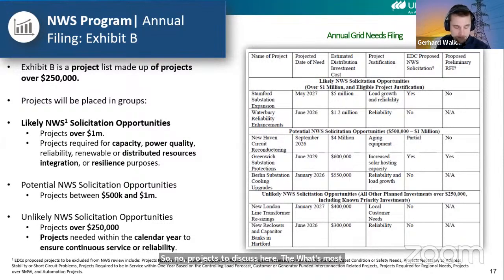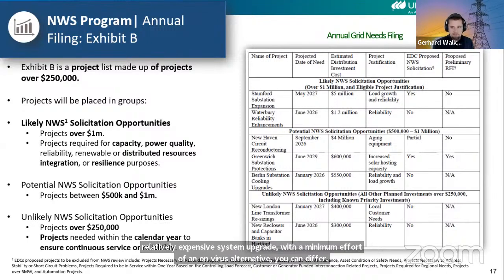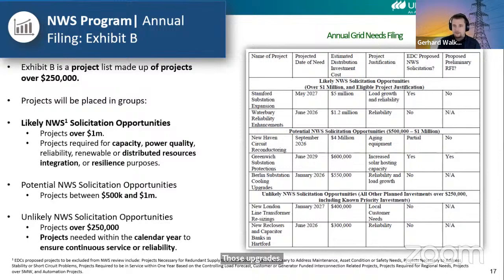What's most likely? Well, there are a couple of reasons why NWAs typically fail. What we've seen is the most viable NWAs are those with a minimal capacity need that triggers a relatively expensive system upgrade, where with minimal effort of a non-wires alternative you can defer those upgrades. NWAs scale pretty significantly cost-wise the larger the deficit gets. If we're talking multiple megawatt sizes, that's where non-wires alternatives typically scale very expensively.